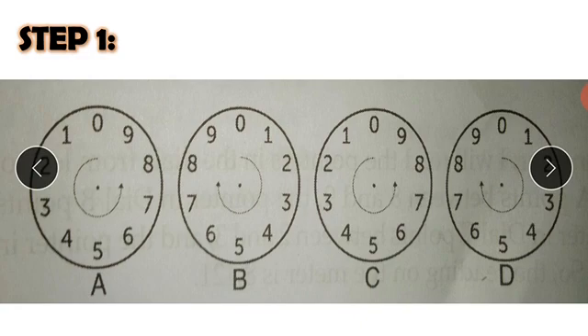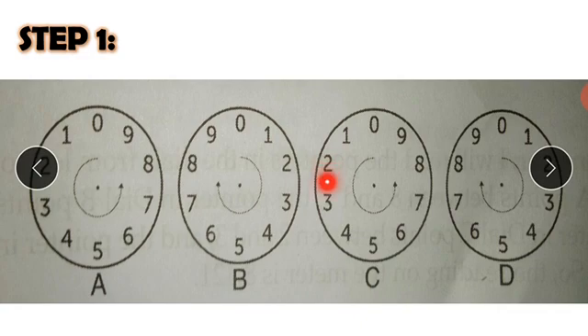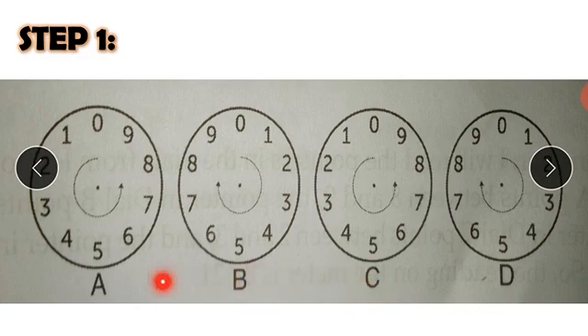The pointer on dial D must complete one full revolution from zero back to zero before the pointer on dial C moves to one. After each revolution of dial D, pointer C advances by one. After a full rotation of dial C, dial B moves to one. The sequence goes from dial D to C, then B, then A. The same procedure applies between dials B and C, and dials A and B.